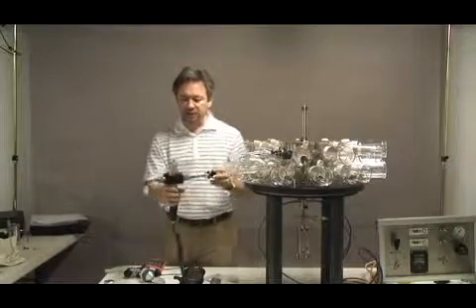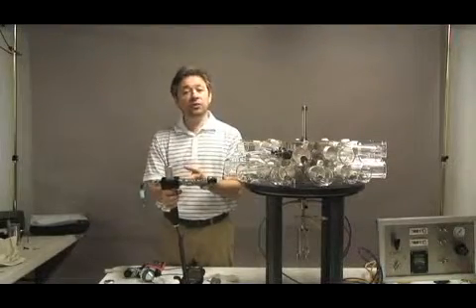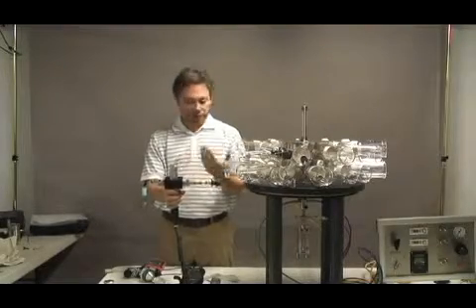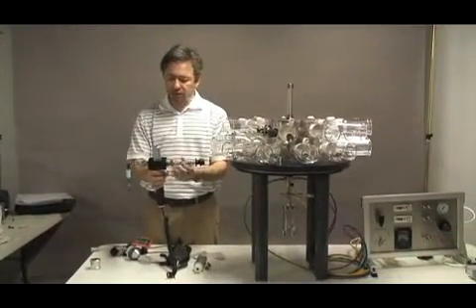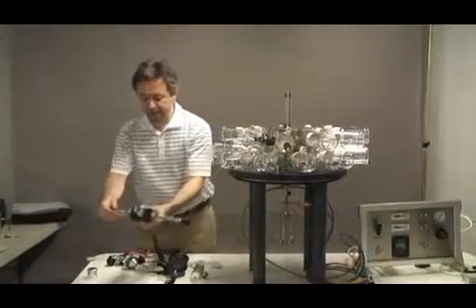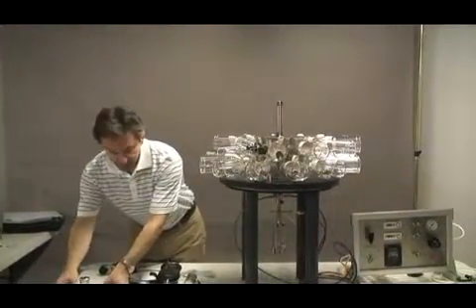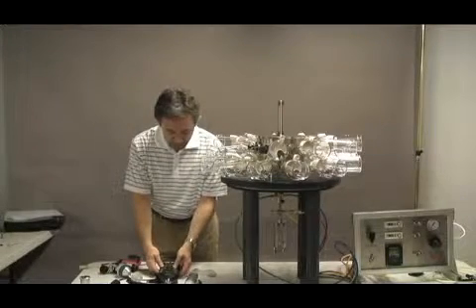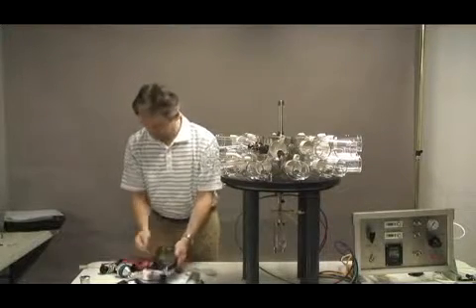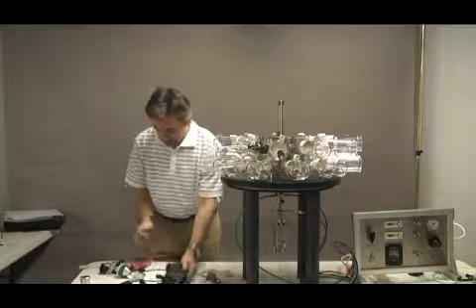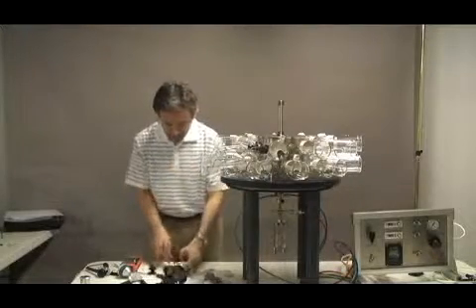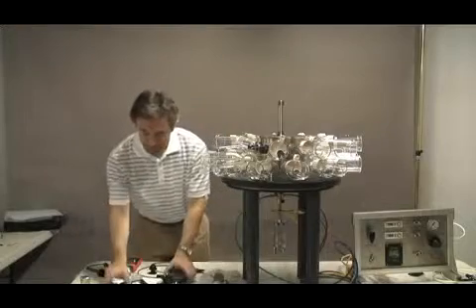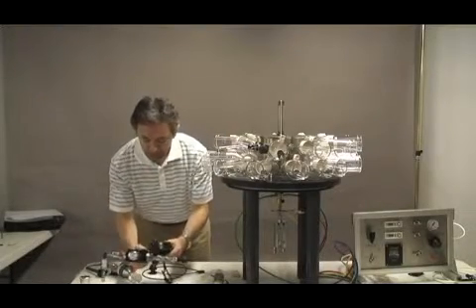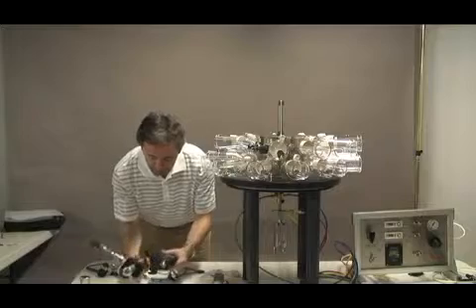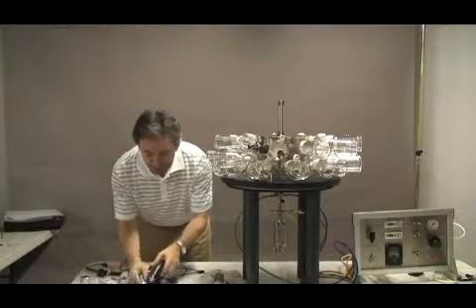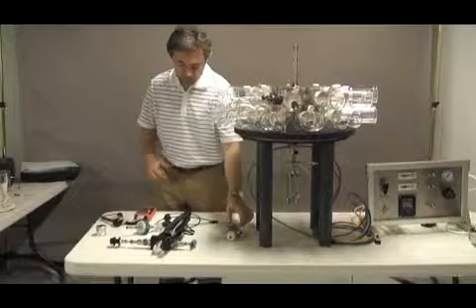The real-time aerosol probe, once you put in the clear lens adapter, there is no need to remove it again. You just stow it away safely somewhere. Make sure that you turn off the unit, disconnect it from your computer, your data cable, disconnect it from the power cord, and safely attach the unit into the probe and stow it away.